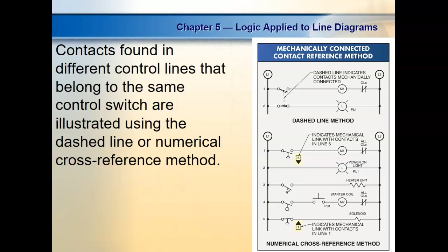All right, so you should always have a signal, a decision, and an action. That's pretty self-explanatory. Between L1 and L2, you should have some sort of something telling your circuit, yes, you're on, no, you're off, right? Then you have something that's going to be doing something else, your load. In the action section, there's not always something making a direct decision though. You do a very simple circuit where you just have a push button and a motor relay. You don't really have something trying to make a decision, you just have something you're turning on. Okay.